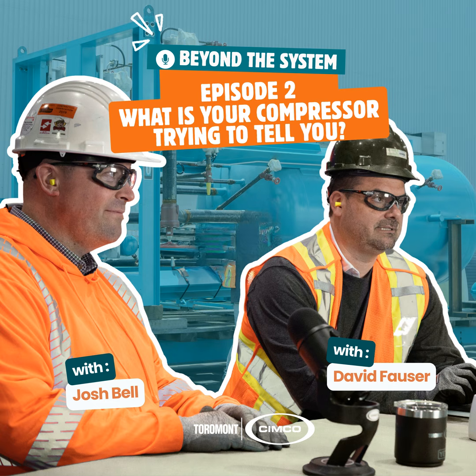But on the more industrial application, you're going to probably see big screw compressors just based on the sheer volume of work they can do in a smaller footprint than a reciprocating machine. And then in ice rinks, you're going to see a variety of screws and recips, more of the mini screw type compressor or the reciprocating compressor. I would say probably the majority of ice rinks, you're going to see reciprocating machines.